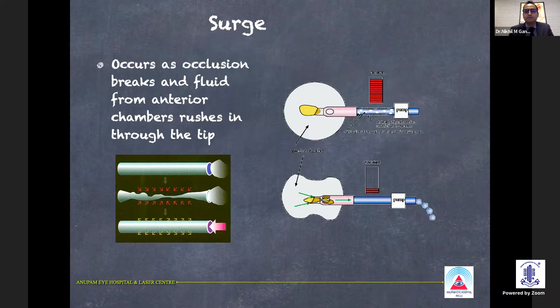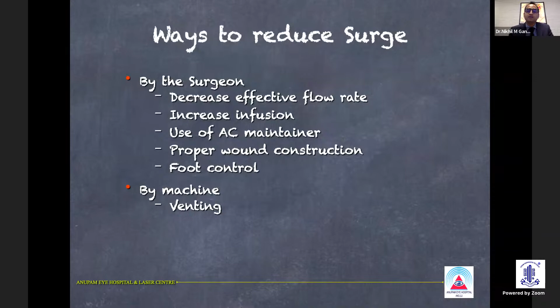Coming to the surge, which occurs as occlusion breaks and the fluid from the anterior chamber rushes through the tip, which leads to the posterior capsular rupture, which I have seen myself whenever I had a high vacuum kept in the settings. So the ways to reduce the surge are by the surgeon and by the machine. By the surgeon, you decrease the effective flow rate, increase infusion, and use the AC maintainer, proper wound construction, and foot control. And by the machine, it is by venting.